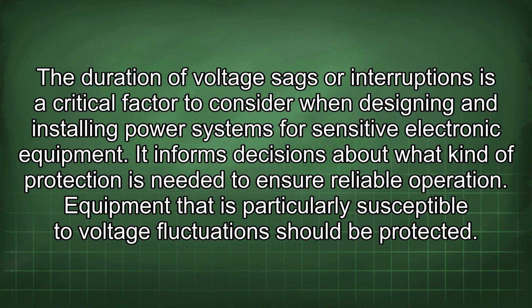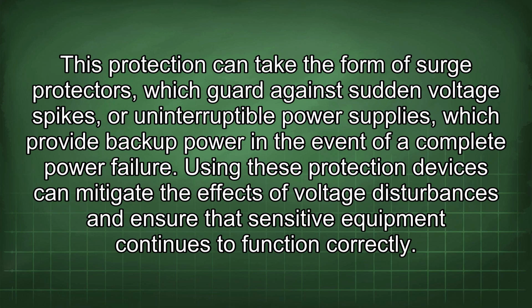The duration of voltage sags or interruptions is a critical factor to consider when designing and installing power systems for sensitive electronic equipment. It informs decisions about what kind of protection is needed to ensure reliable operation. Equipment that is particularly susceptible to voltage fluctuations should be protected. This protection can take the form of surge protectors, which guard against sudden voltage spikes, or uninterruptible power supplies, which provide backup power in the event of a complete power failure. Using these protection devices can mitigate the effects of voltage disturbances and ensure that sensitive equipment continues to function correctly.